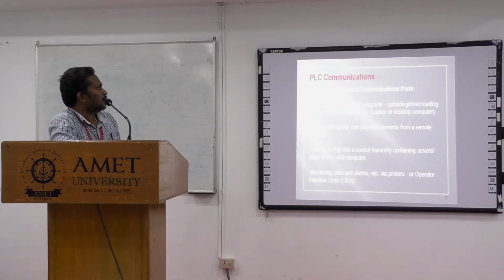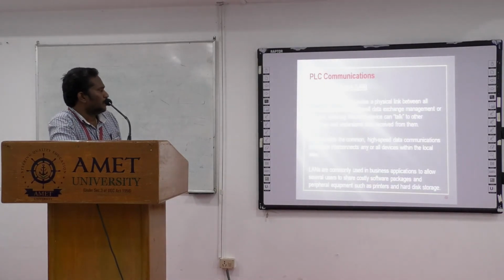PLC communications. Normally we communicate between a programming device and the PLC using communication ports. Changing resident PLC programs, updating, downloading and uploading from a supervisory control, we have to go for communication devices. Forcing I/O points and memory elements from a remote terminal, linking a PLC into a control hierarchy containing several sizes of PLCs and computers, monitoring data and alarms, etc. via printers or operator interface units, we need communication devices and communication ports. These are the usual communication ports used in PLC communication.